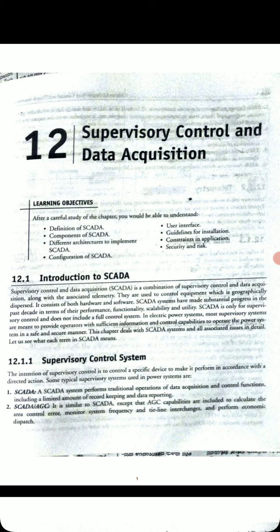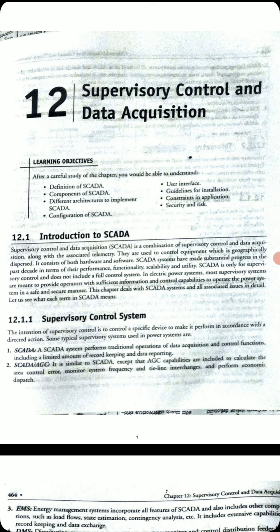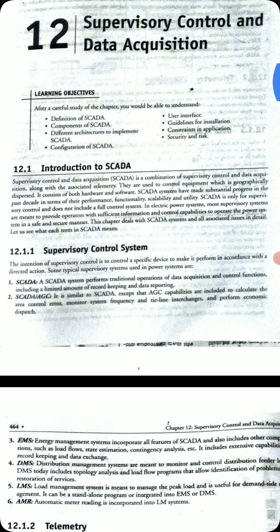So we will see some typical supervisory systems. First is SCADA, a system which performs traditional operations of data acquisition and control. Second is SCADA plus AGC - SCADA with supervisory control and data acquisition, plus AGC which has the capacity for area control error calculation, monitoring system frequency, tie-line interchanges, and performance of economic dispatch. Apart from traditional SCADA, the AGC control action is included; this is called SCADA plus AGC.